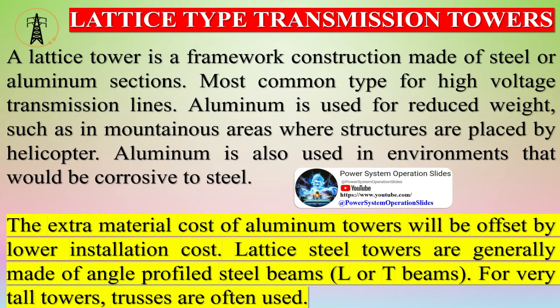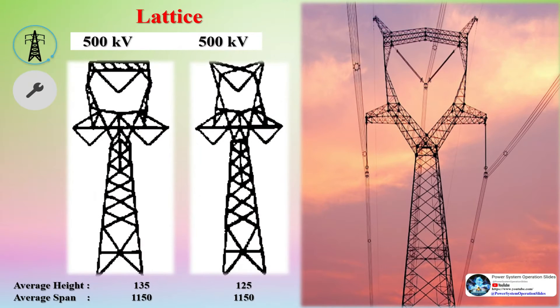Lattice towers are the most common type of transmission towers, consisting of steel frames that form a triangular or square shape. They are strong, flexible, and easy to assemble and transport. Lattice towers can support multiple circuits and span long distances, making them suitable for most terrains and weather conditions. However, they have drawbacks such as high maintenance costs, visual impact, and susceptibility to corrosion and bird collisions.